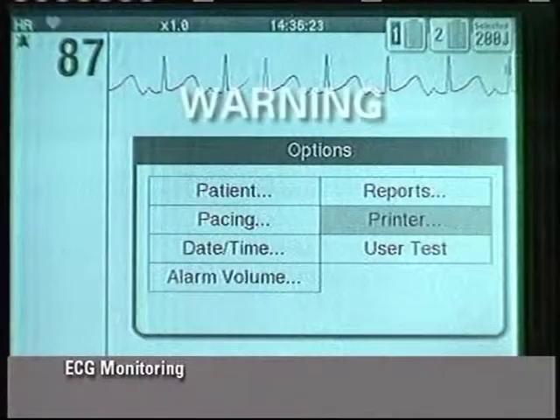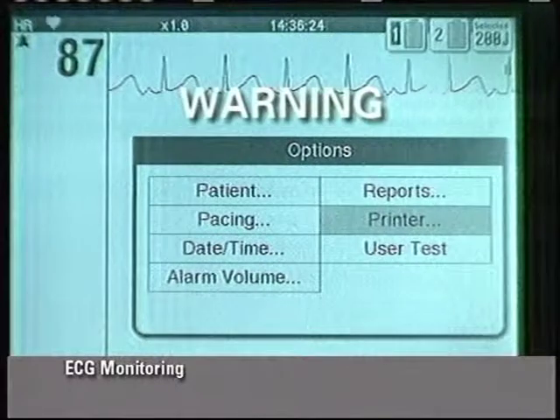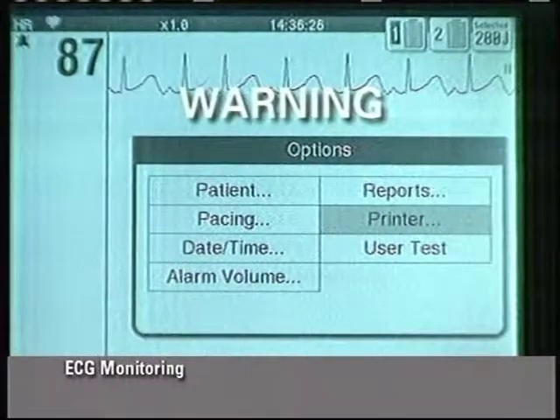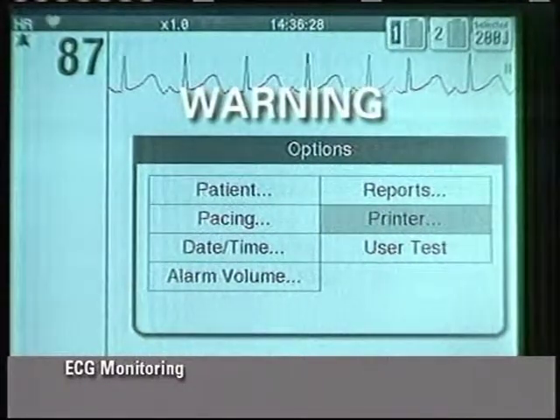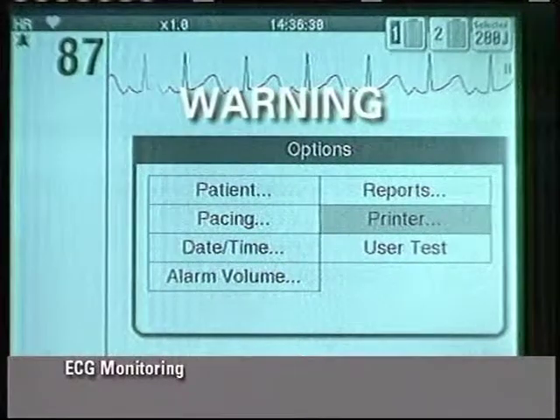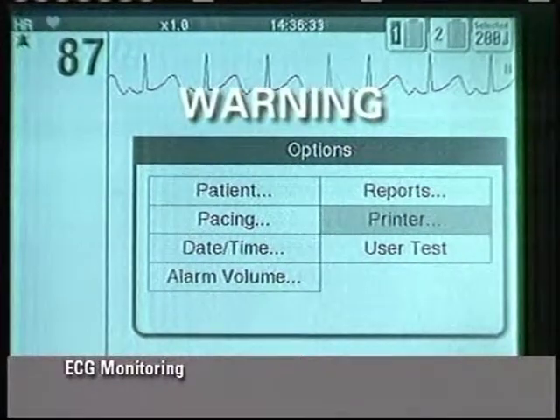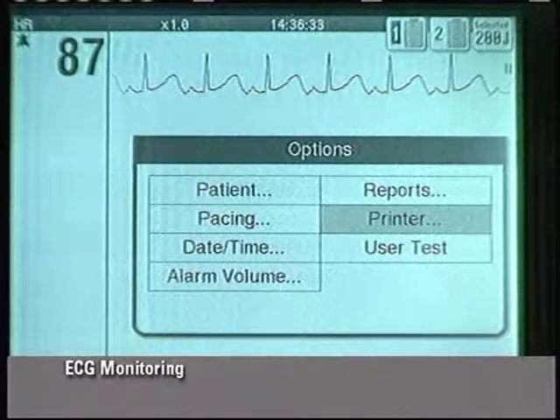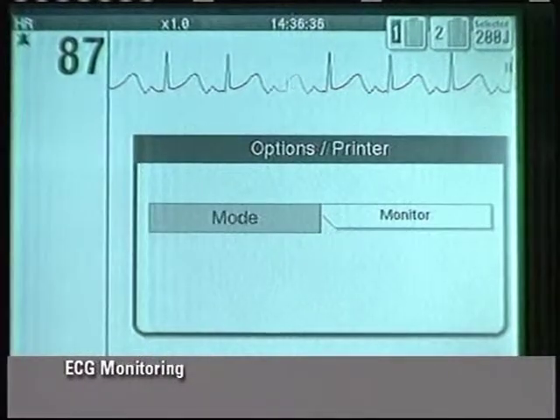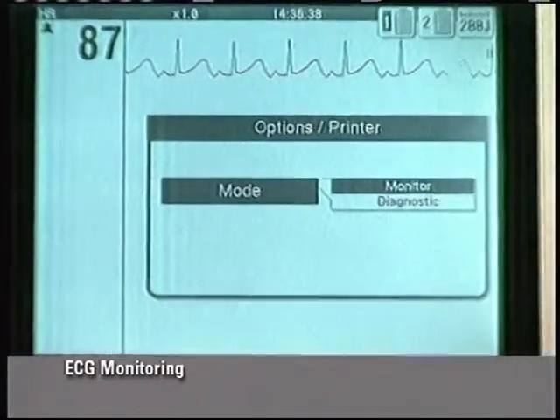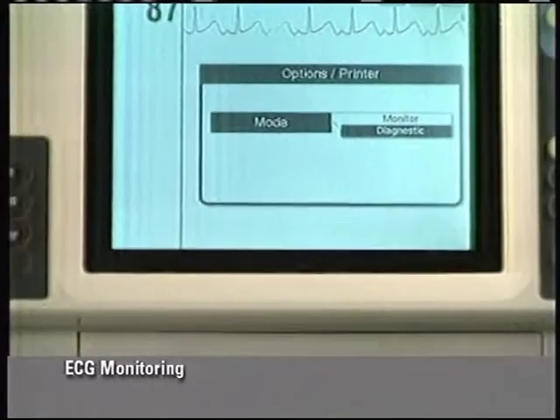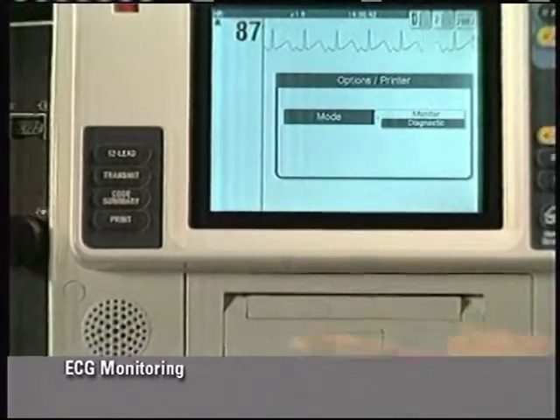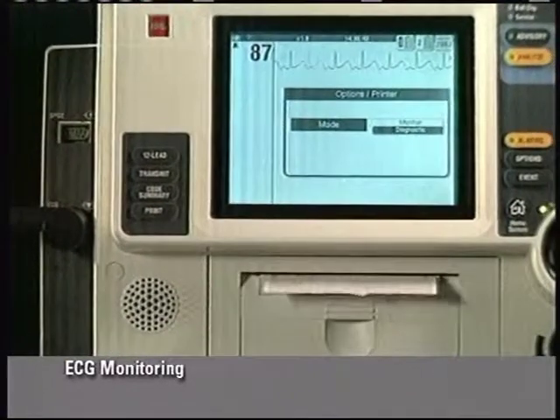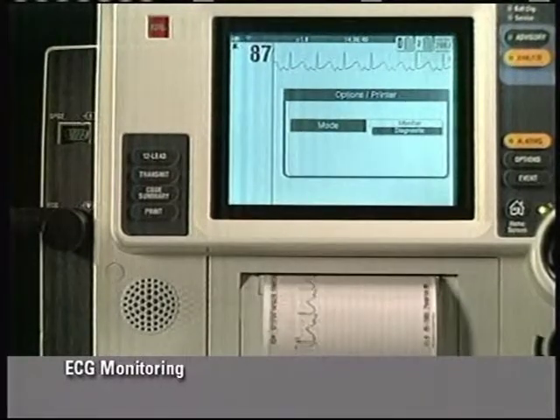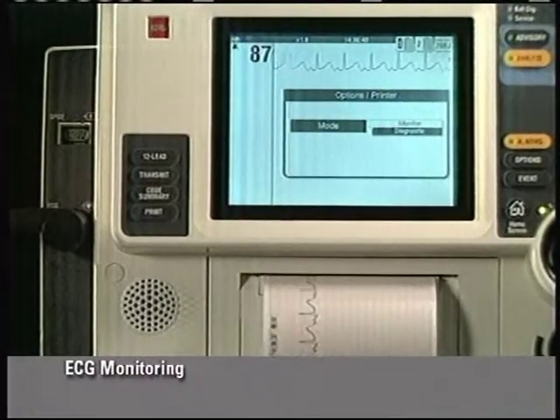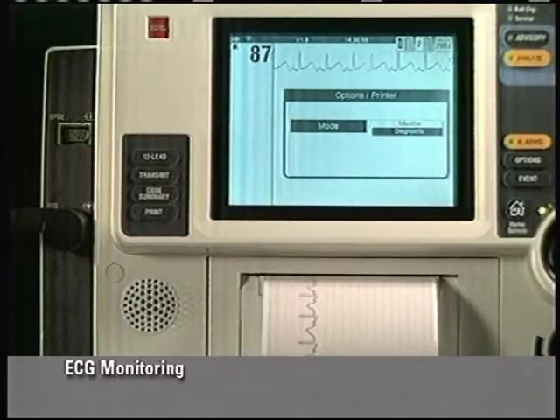The frequency response of the monitor screen is intended only for basic ECG rhythm identification. It does not provide the resolution required for diagnostic or ST segment interpretation. For diagnostic, ST interpretation, or to enhance internal pacemaker pulses, attach the ECG cable and print the ECG in diagnostic mode or obtain a 12-lead ECG. This concludes the ECG monitoring section of this video.